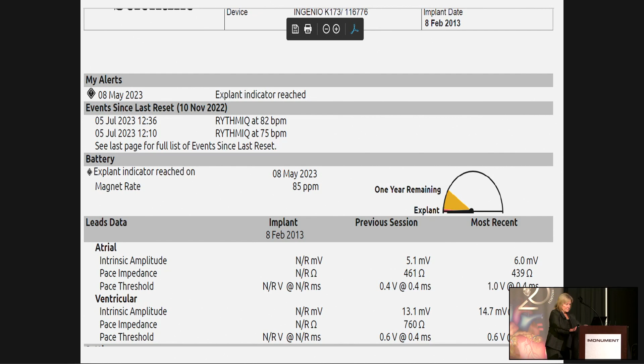A threshold is the least amount of electrical energy coming out of the device that's going to capture or pace the heart. It also measures lead impedance, which can be an indicator if there's a fracture or a break in the wire. The impedances will be lower than they're supposed to be, or higher. And this is more information that's printed out with the device interrogations.